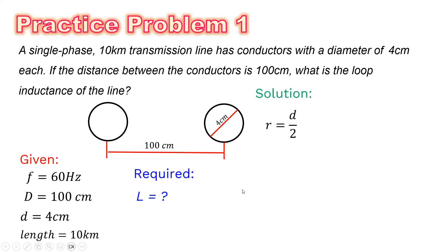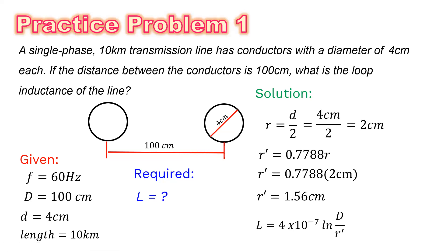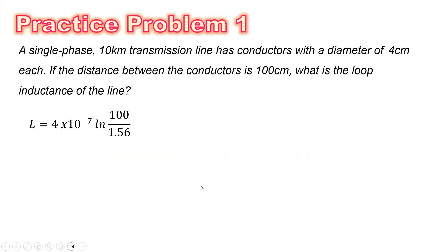To solve that, let us solve for the radius first. Radius is equal to diameter divided by 2, so that is 4 cm divided by 2, which equals 2 cm. So we can now solve for R prime, or the GMR. That is equal to 0.7788 times R. So we simply plug in the value of the radius, which is 2 cm, giving R prime equal to 1.56 cm. Now we can substitute all the given values into our equation: inductance is equal to 4 times 10 to the negative 7, natural logarithm of D over R prime.